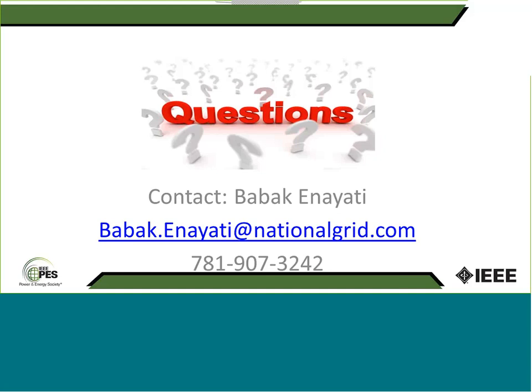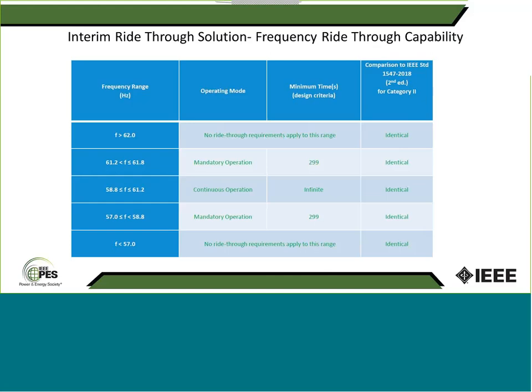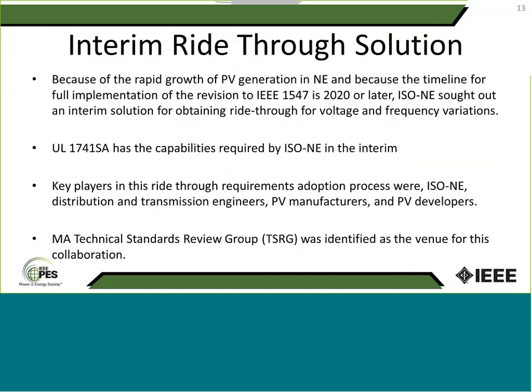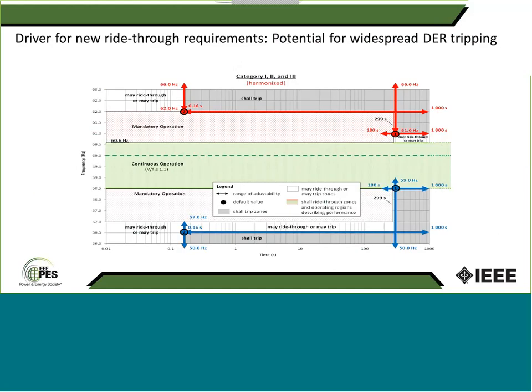The first question is really a set of two questions, Babak, and they're related, from two different people. The question is: is there an inherent conflict between momentary cessation and PRC-024, and how should the industry plan for this conflict? And the second question, a follow-up, was: some grid codes require injection of current during the fault. If the smart inverter stops providing current, it will not comply with this request. I believe that's a European grid code consideration. So I guess the basic question for 1547 has to do with whether there's an inherent conflict between momentary cessation and PRC-024.